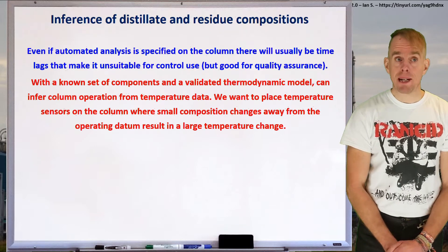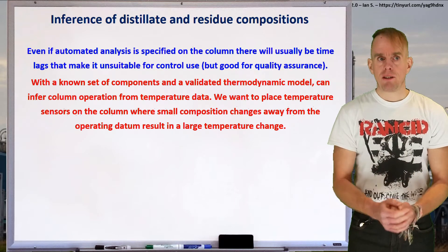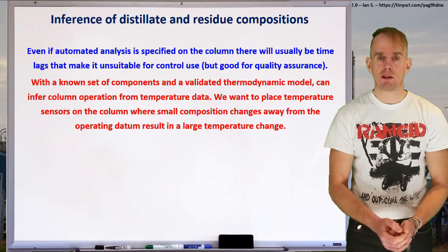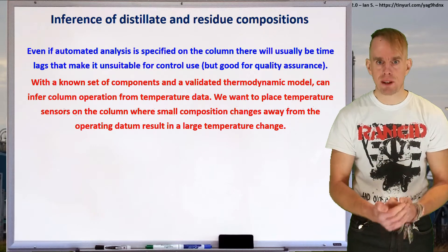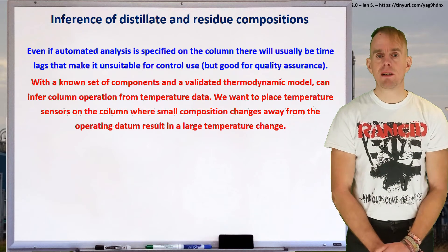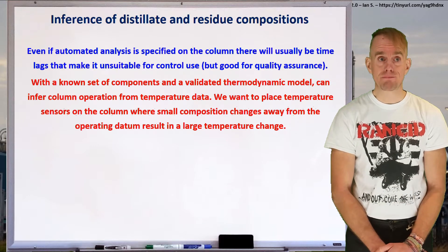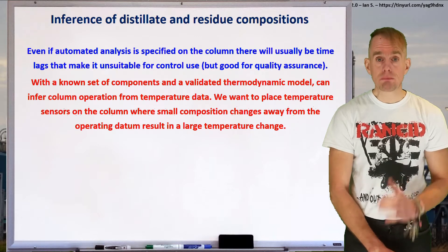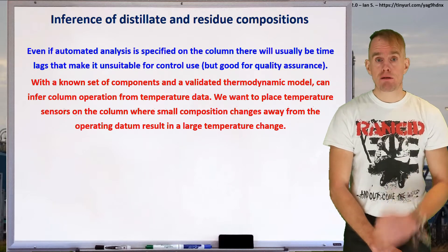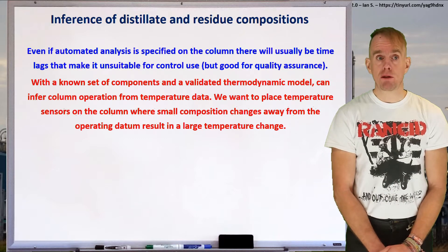So, let's start at the beginning. How do we figure out what our column's doing? The key problem is that automated analysis equipment usually takes time to come to a result, even if you can find analysis equipment for the chemical species that you've got. Very often, the amount of time taken is going to be too slow for control to be used from that. Automated analysis equipment is very good for quality assurance. Laboratory testing is very good for quality assurance. Neither of these are very good for column control.